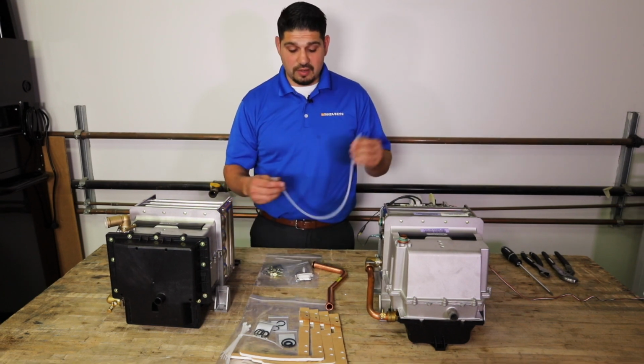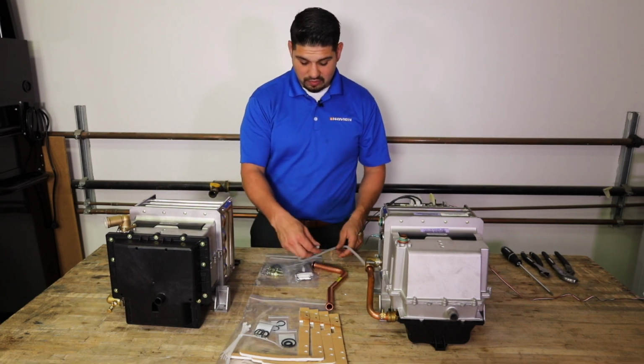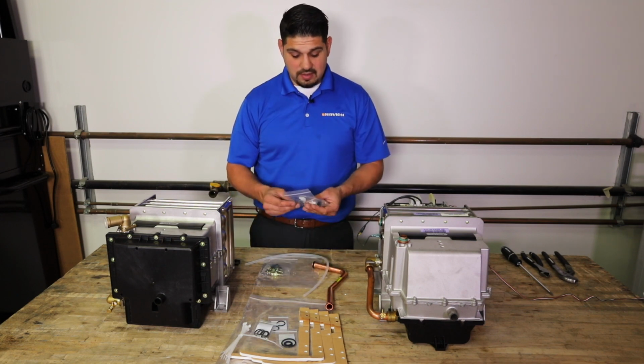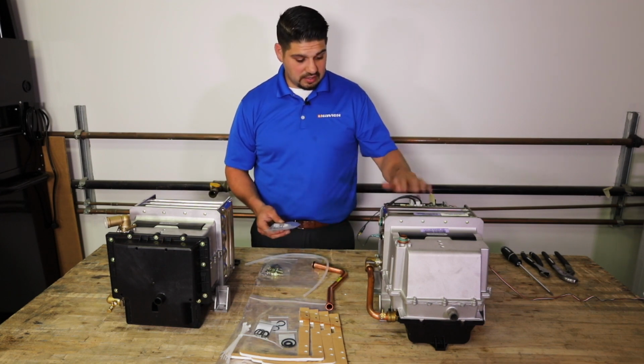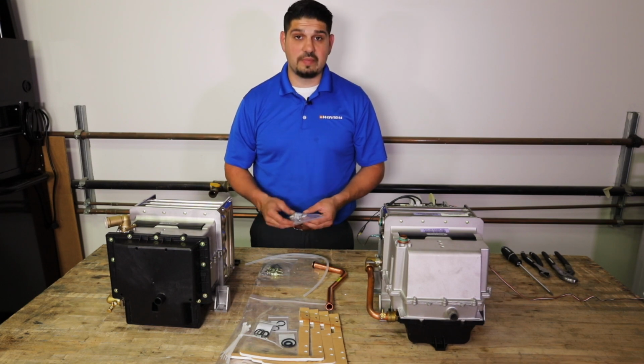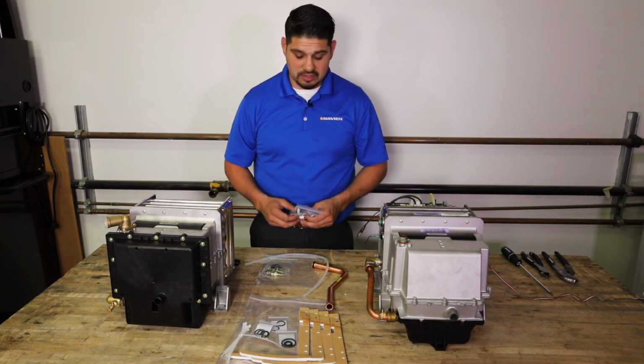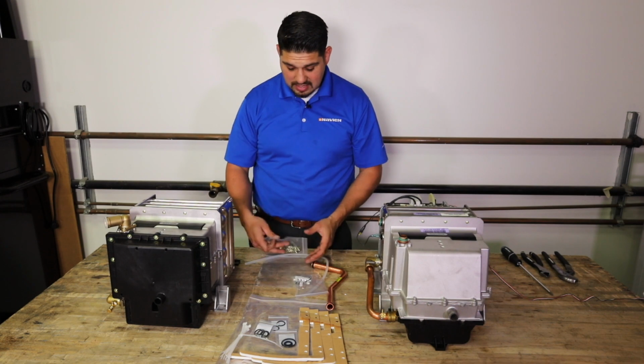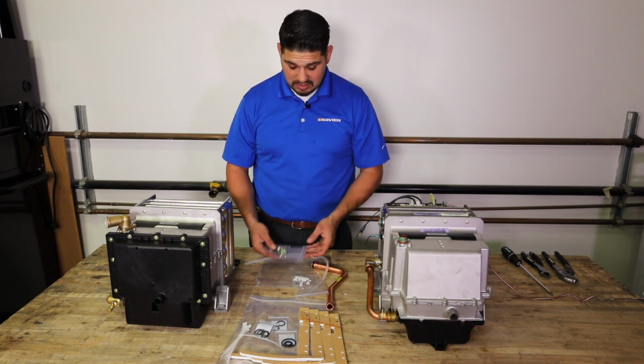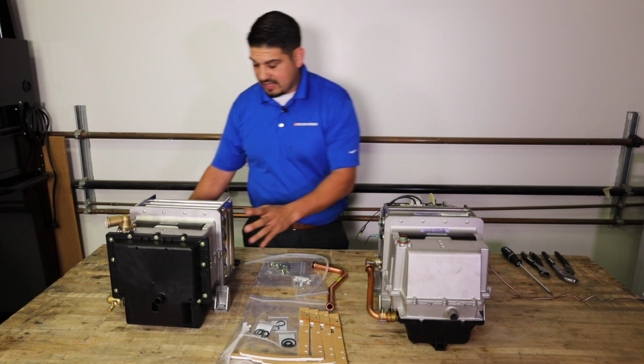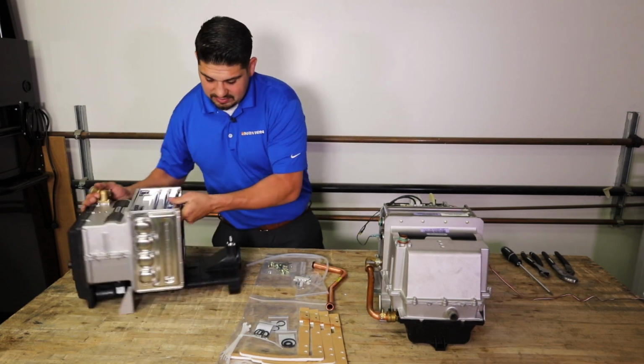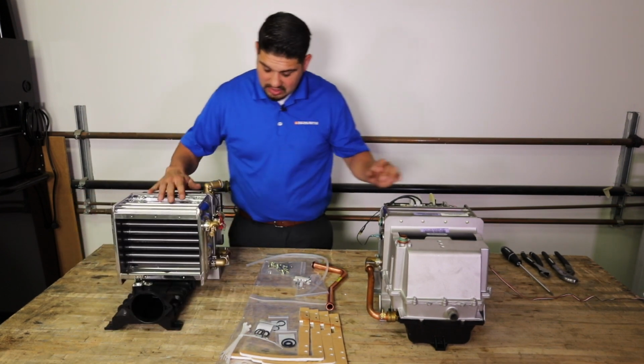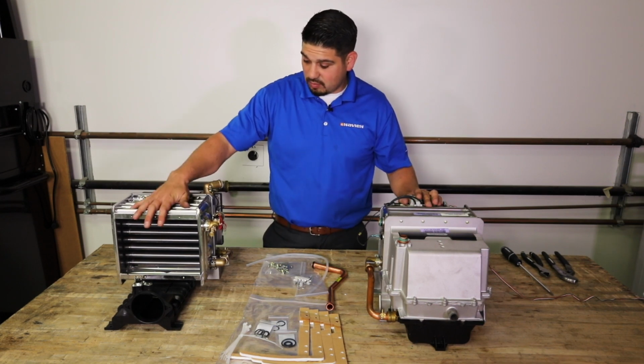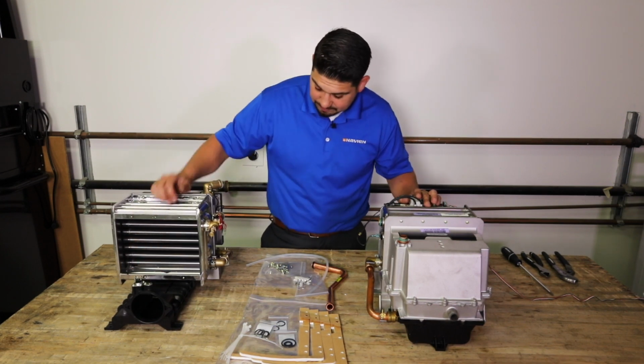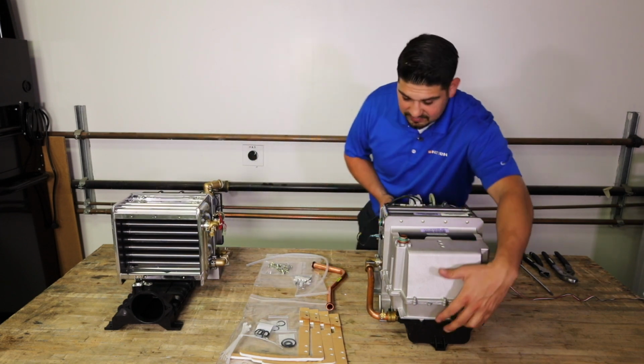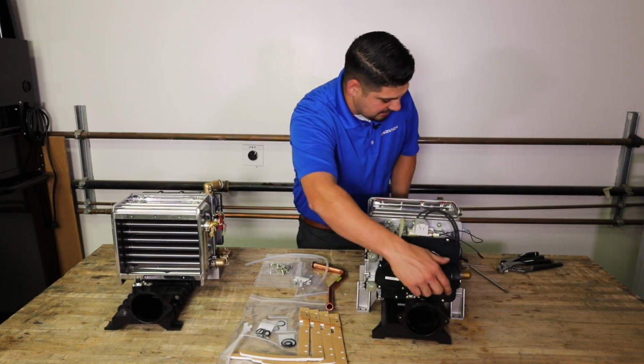A slightly longer silicone hose for our bleeders. A new flame rod, because the old flame rod's going to have some buildup and some deterioration just over wear and tear. So it's always good to have a new flame rod. And all the hardware that we're going to need. What we're going to do to get this ready to go back into installation is, let me go ahead and flip these around. As you can see, all that we were provided was our primary and secondary heat exchanger with their exhaust duct.